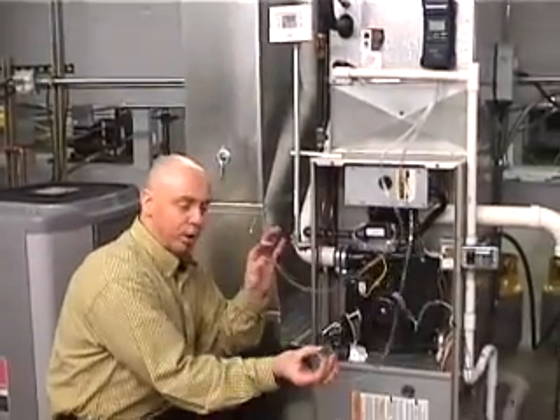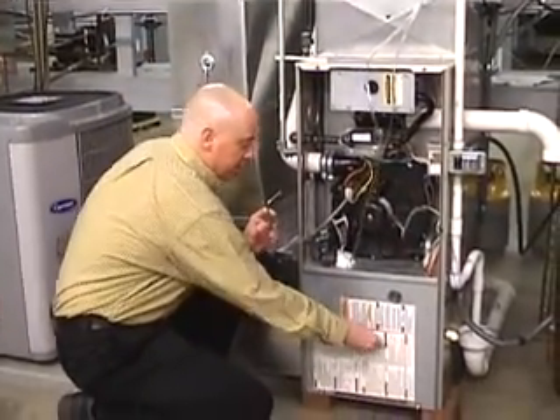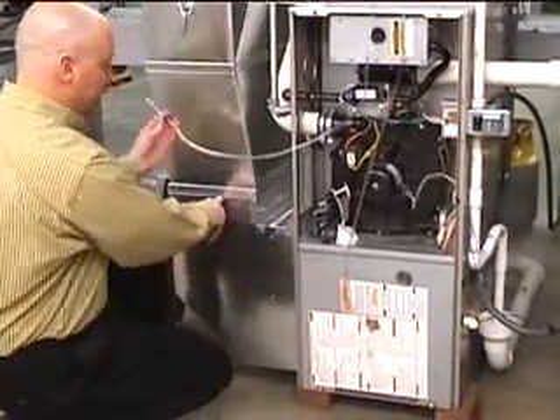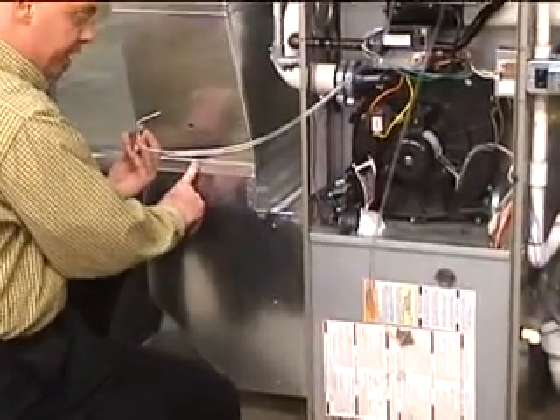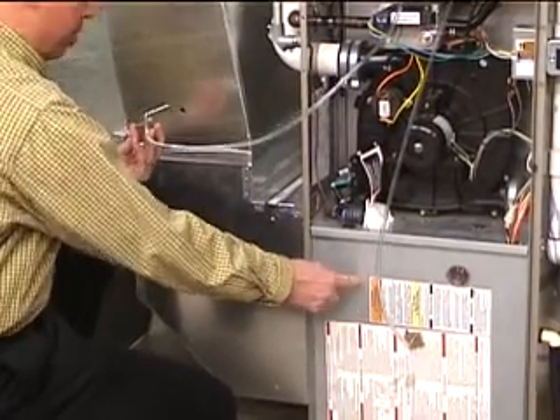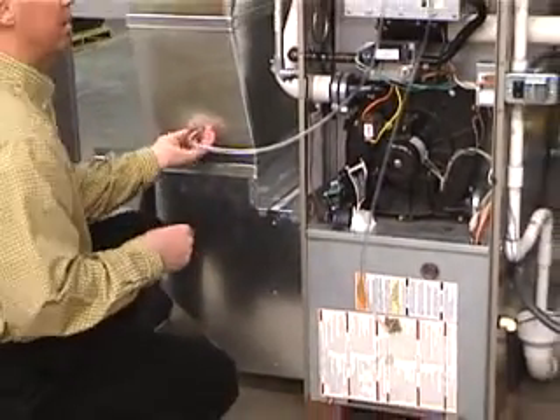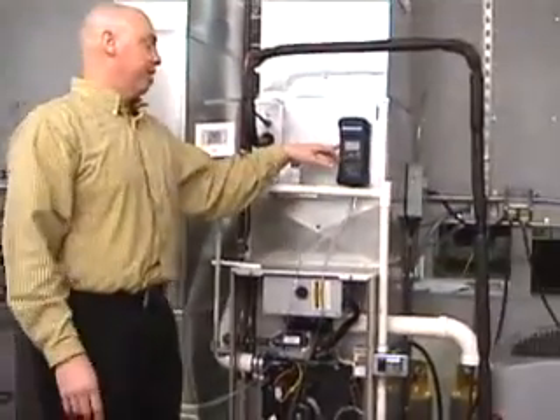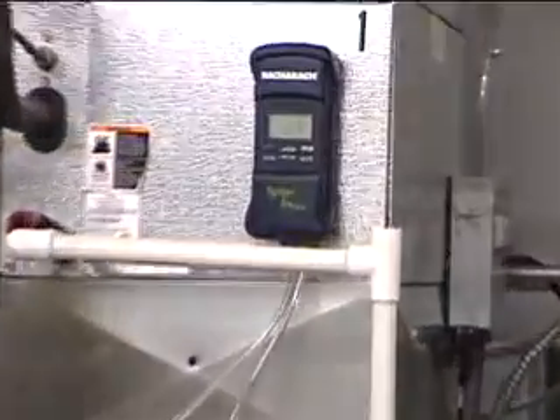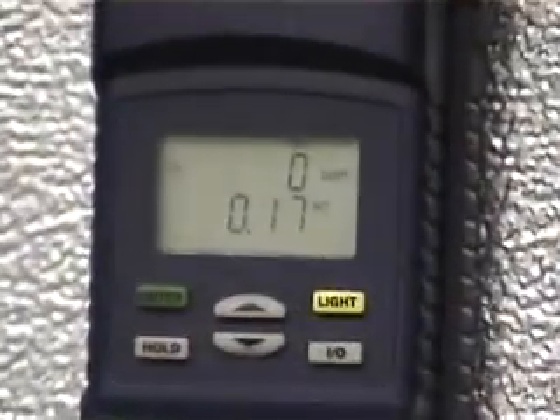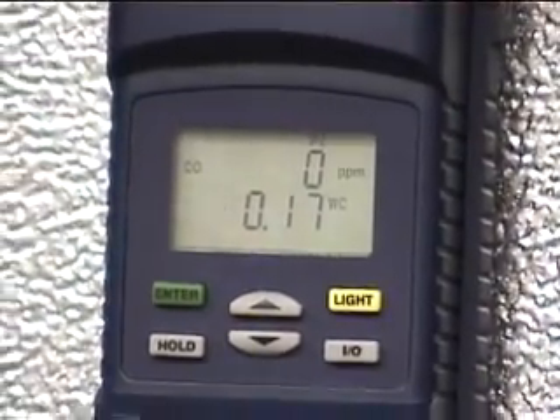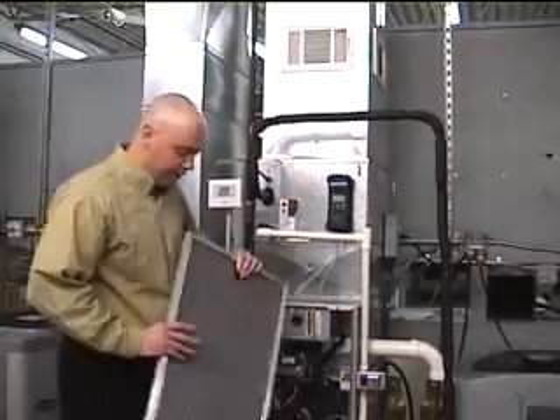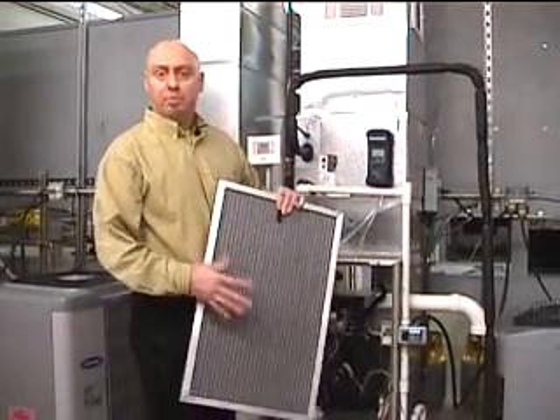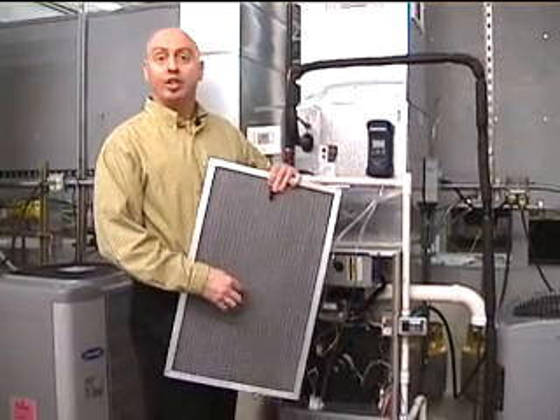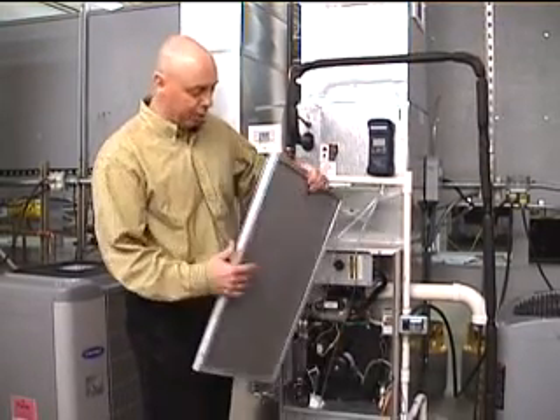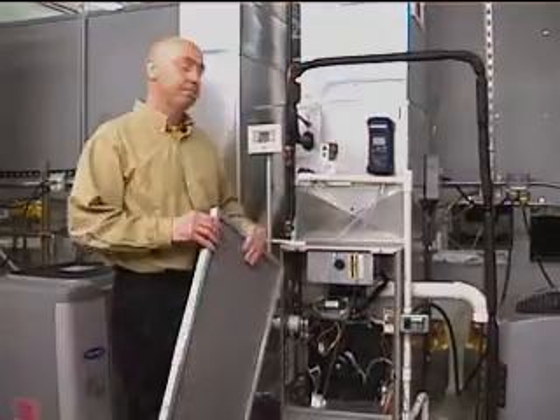And again, I take my two probes and I put one between the filter and the furnace, and the other one's across the filter. So I'm going to have one on this side of the filter, the inlet, and the other side of the filter where the inlet of the blower motor is. You can see my pressure drop for this filter is 0.17, which is a little bit restrictive. But you've got to watch these really highly restrictive ones, especially the 1-inch filters. Filters like this have a high value of picking up, but they're only 1 inch thick. It's very hard to get air through those filters. So those can be really bad and can be damaging to a system.